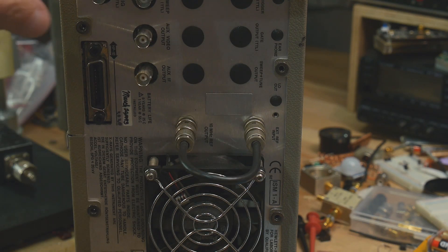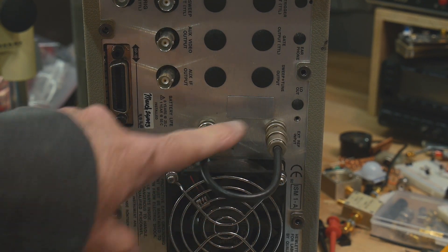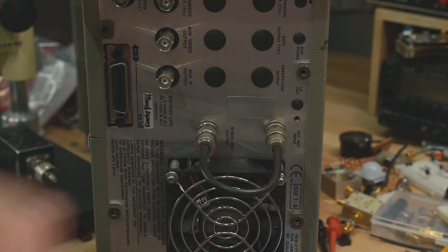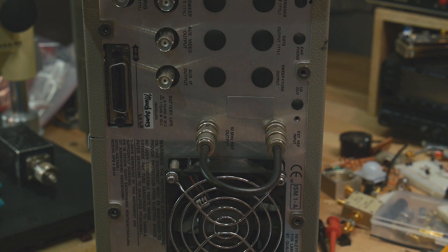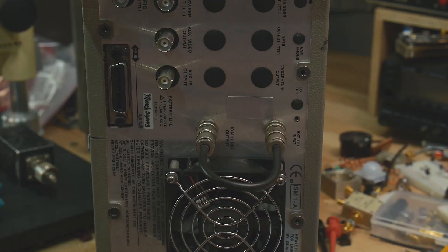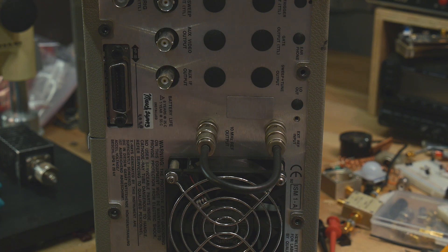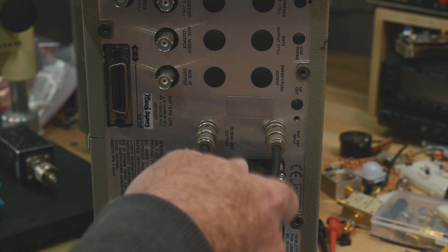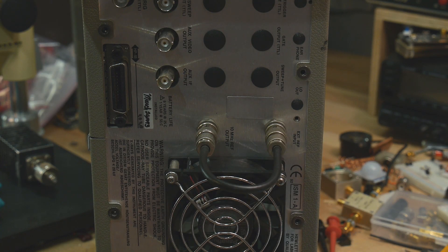While I'm back here — if you ever pick one of these up, it doesn't work without this cable. You need a cable that runs between these two BNCs. This one says 10 MHz Ref output, and this says external Ref input. You can supply your own 10 MHz from outside, like from a Rubidium standard. But if you're using the internal reference, it's not hardwired inside — there's no switch. You need this cable connecting the two, otherwise it'll show reference unlocked or oscillator unlocked. If you find one of these, it might be missing this cable; you'll need to build one or find one.